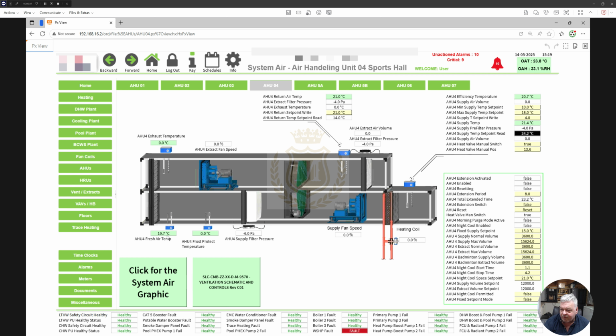So we've got 19.7 outside air, and we're recirculating this, and then we're giving 20.7 at the moment. So there's actually no heating coil on, but we're transferring a little bit of that air, which is coming back at 21, mixing it with the 19.7 and bringing it through back into the building again. I don't know if there's any more examples that I can show you.